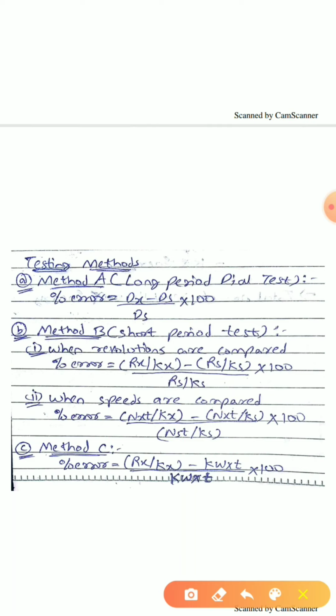The first energy meter, for example, let me take it to be the meter that I am testing, and let me take this to be the standard meter. Now this standard meter will register, for example, some amount of energy. I will compare with the standard meter whether the meter under test is showing the same supply or not.